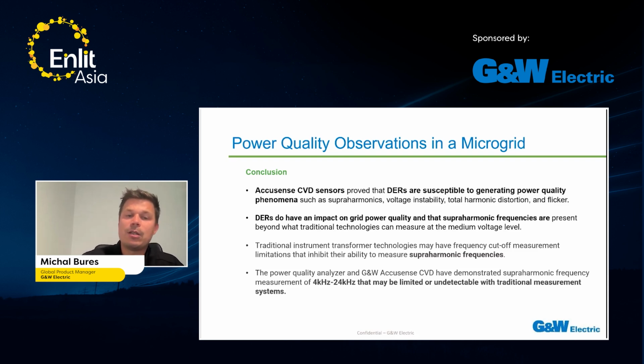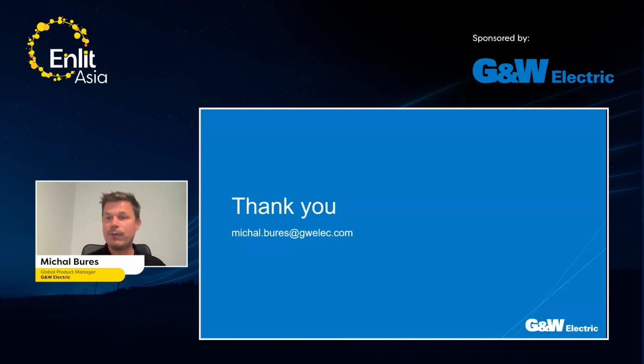But with traditional instrument transformers, probably thanks to the frequency cutoff, we are not able to detect or measure supraharmonics. And you can see that we measured them from 4 kilohertz to 24 kilohertz. So it may be limited or undetectable with a traditional measurement system, VTs and CTs. This is the reason why high accuracy measurement is required, and you can see it in a real use case. So from my side, this is everything.